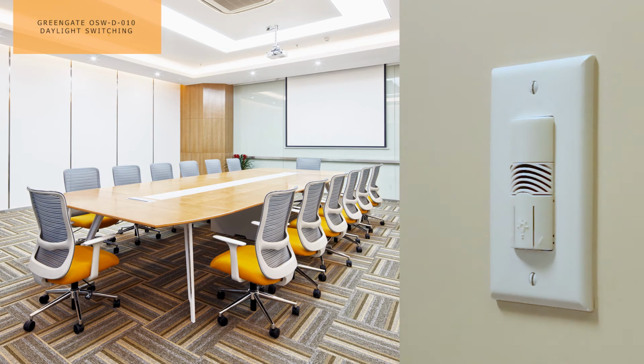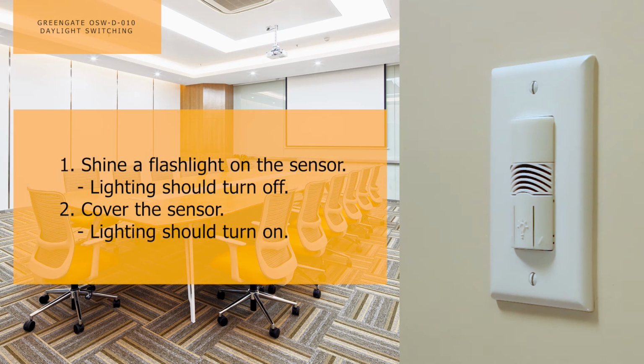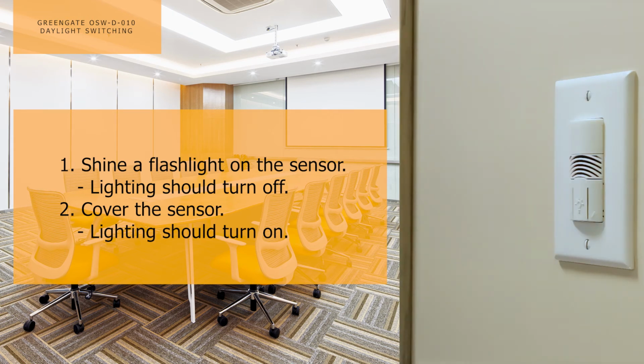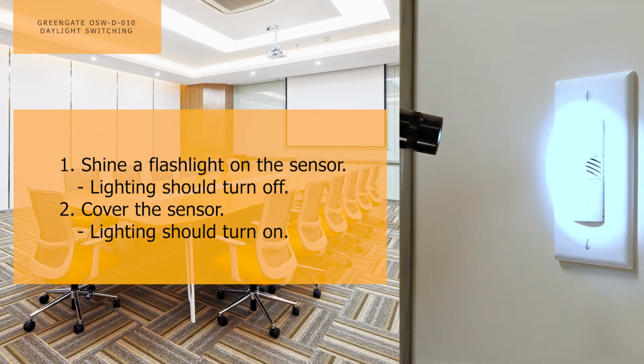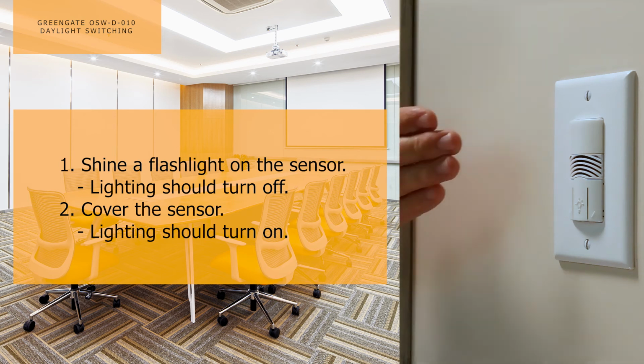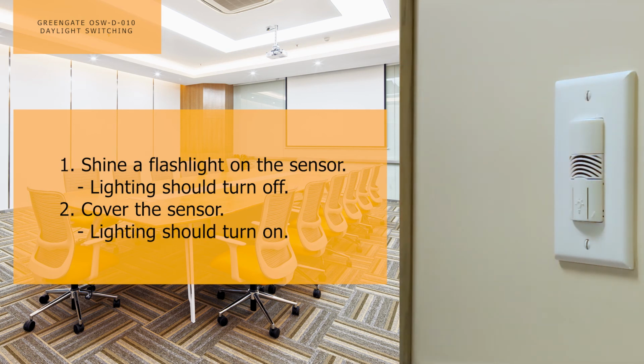Once the LED stops flashing, the sensor will begin a 30-second capture of the ambient light level and then enter a 5-minute testing period. After 30 seconds, test the sensor. First, shine a flashlight on the sensor. The lighting should turn off. Next, cover the sensor. The lighting should turn on.